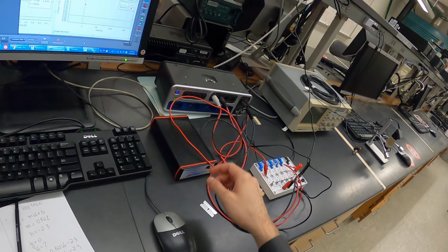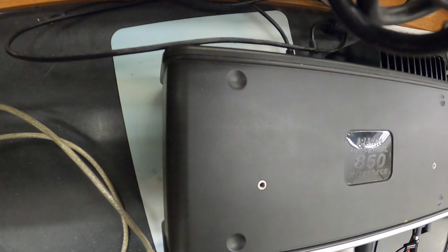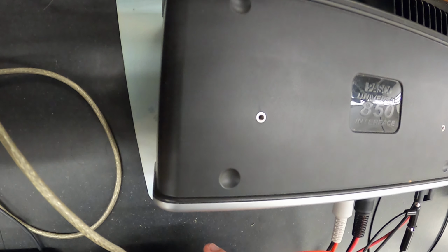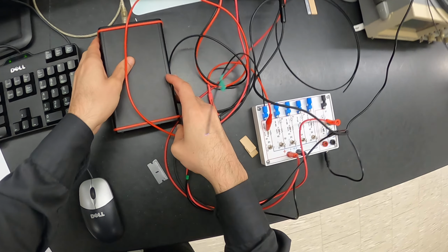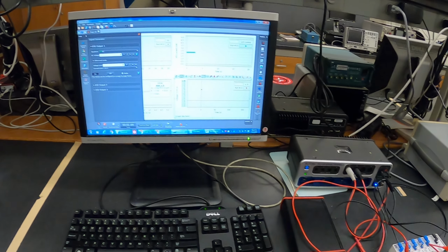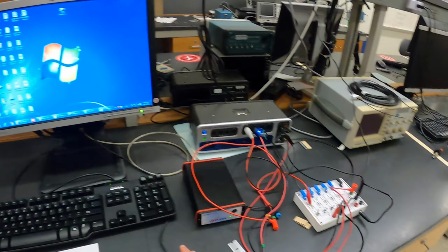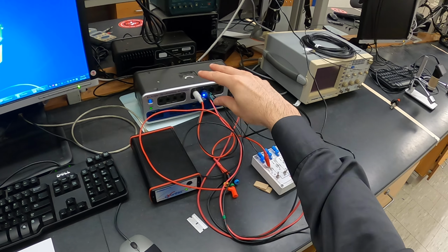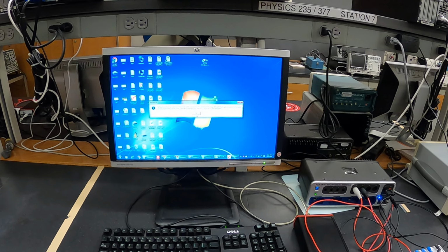And this spectrometer, there's a switch in the back, so we will turn on to the USB mode here. So we turn this on, so the power on LED here is on. And now we can open the software. It's this AvaSoft 7.5. Okay, the spectrometer was connected.